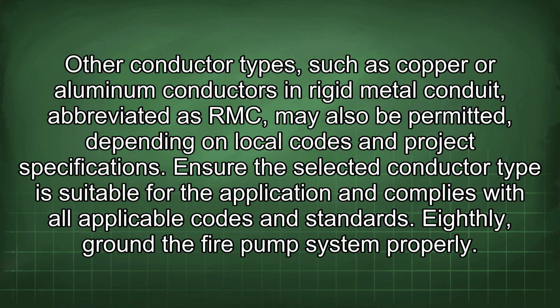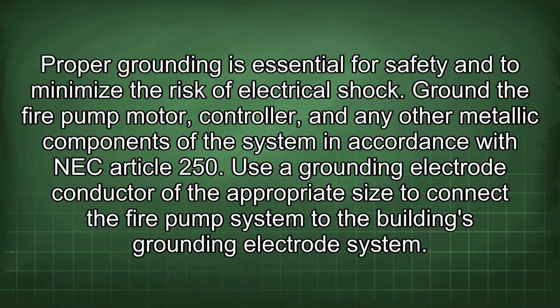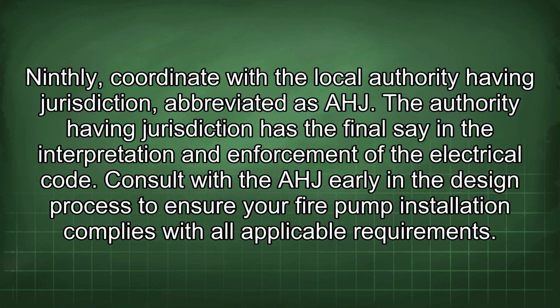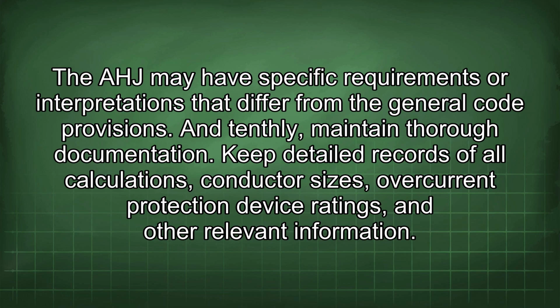Eighthly, ground the fire pump system properly. Proper grounding is essential for safety and to minimize the risk of electrical shock. Ground the fire pump motor, controller, and any other metallic component of the system in accordance with NEC Article 250. Use a grounding electrode conductor of the appropriate size to connect the fire pump system to the building's grounding electrode system. Ninthly, coordinate with the local authority having jurisdiction, abbreviated as AHJ. The authority having jurisdiction has the final say in the interpretation and enforcement of the electrical code. Consult with the AHJ early in the design process to ensure your fire pump installation complies with all applicable requirements. The AHJ may have specific requirements or interpretations that differ from the general code provisions.